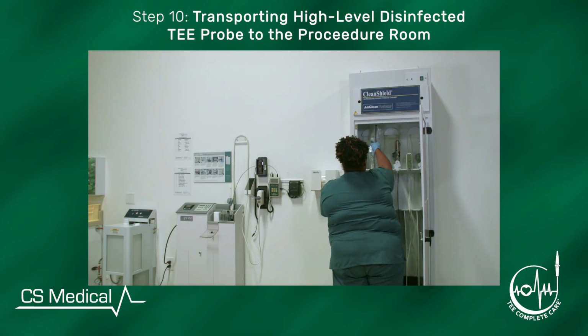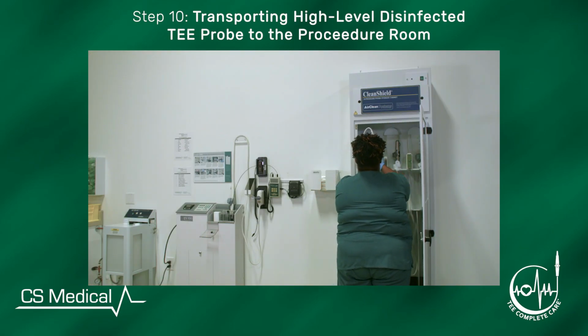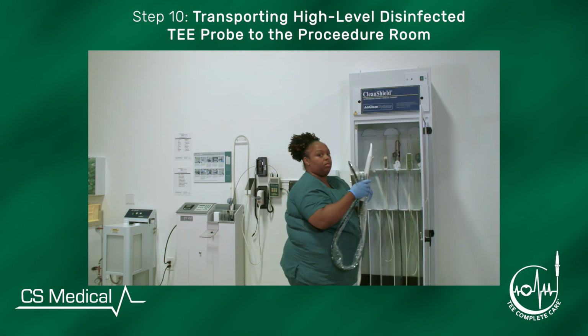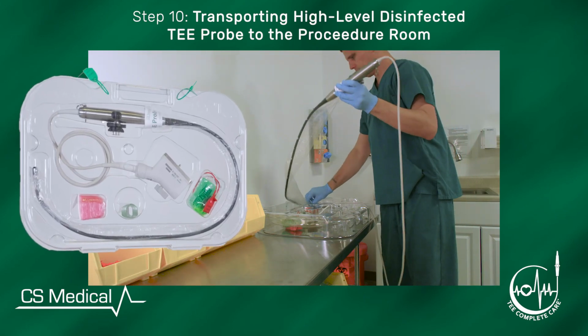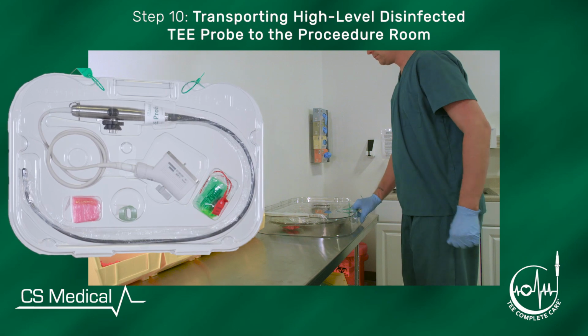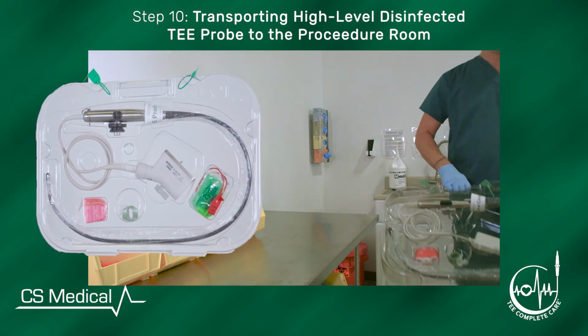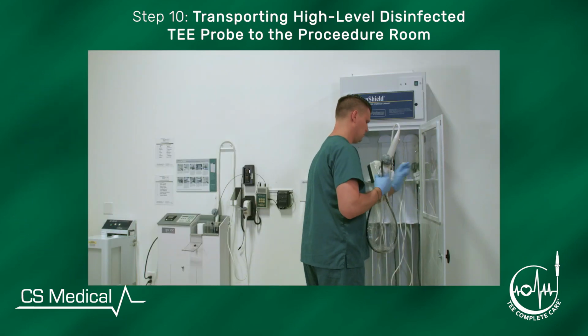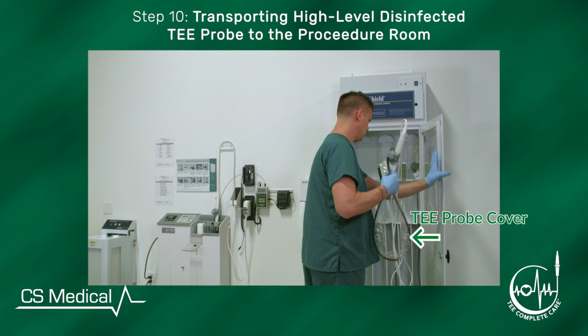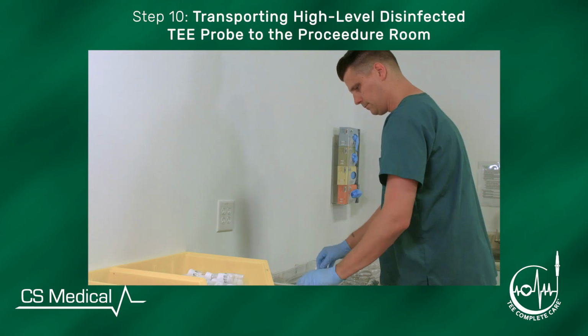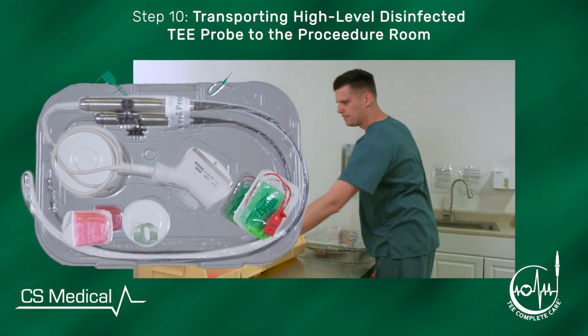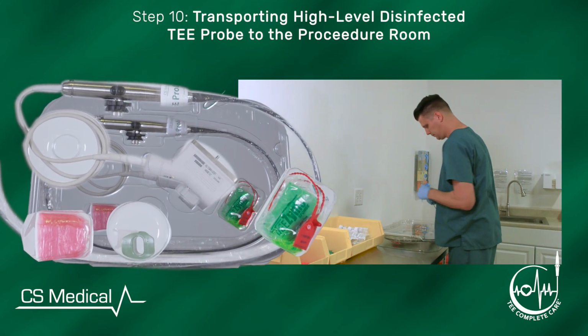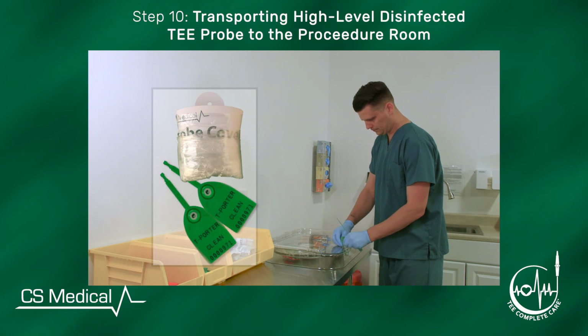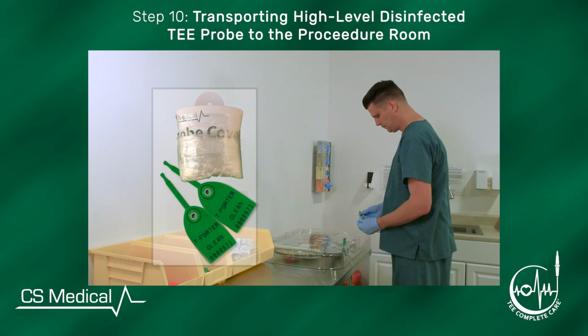A high-level disinfected TEE probe can be removed from the Clean Shield and placed into the T-Porter to allow for safe and secure transportation throughout the healthcare facility. The high-level disinfected TEE probe is placed in a plastic sheath prior to being loaded into the T-Porter. The T-Porter has specially designed compartments for the different parts of the TEE probe. Once loaded into T-Porter, green tie bands, labeled Clean, are used to secure the lid to the case and ensure that the TEE probe does not fall out.